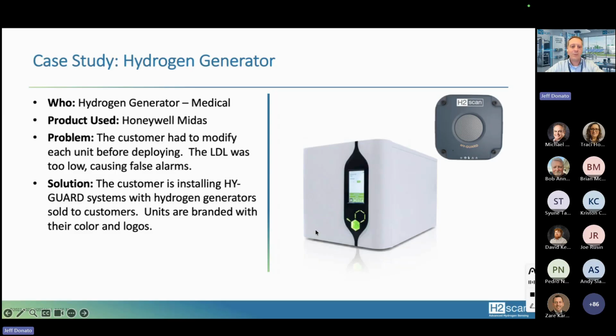So in an example where you're producing hydrogen regularly, you're trying to maintain below 1%. So it makes no sense to try to measure something in a very low ppm level. So we don't have to be that minuscule with our reading. So in this case, sometimes lower readings actually hurt the customer. So in this case, right sizing a sensor to the application is very important.